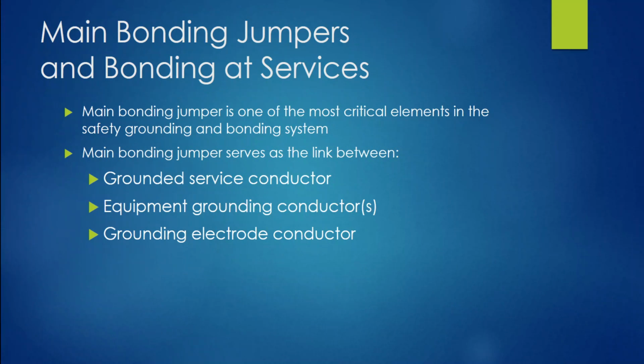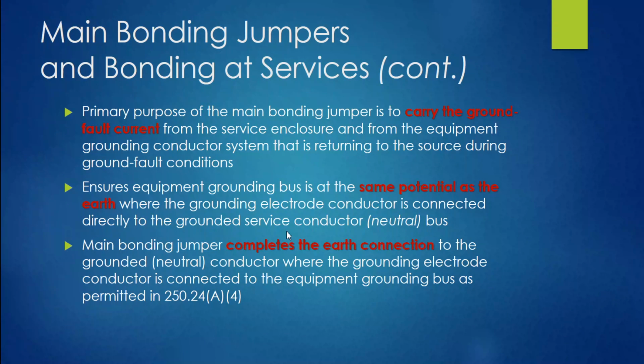All right, so in this presentation, it connects the grounded service conductor, the equipment grounding conductors, and the grounding electrode conductor together. Now let's talk about some purposes here, because we're talking about the main bonding jumper, and it has a distinct purpose.